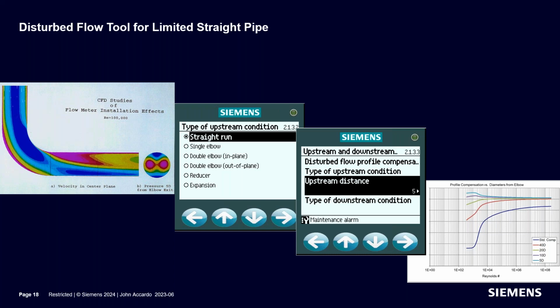So keeping on the theme of the disturbed flow tool, if we look at the graphic in the upper left here, you see a flow coming around an elbow, and you also see a circle there where it's looking down the pipe end on. And that flow profile is anything but what I showed you earlier with the Reynolds number. You have 2 high velocity components, and it's not axial. It's not coming down straight along the pipe walls. It's at an angle to the pipe walls. So this is where the information from the studies at the NIST came into play, and where our straight run tool or disturbed flow tool came into play.